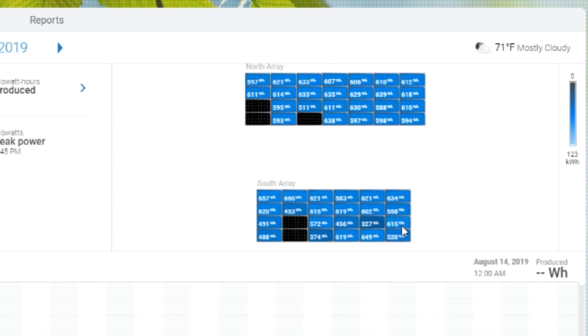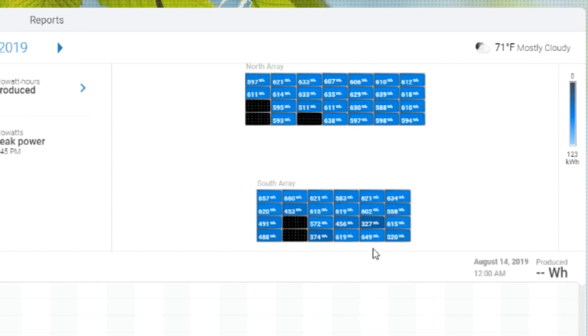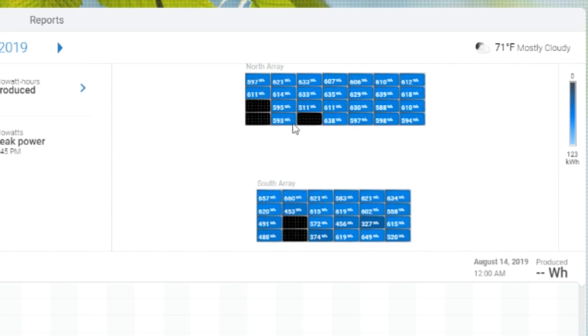Now, I know for a fact that there's no shading here, and it seems to be consistent, this low production. So it gives me a pretty good idea that this system has some issues, aside from just these obvious ones, these obvious inverters or panels that aren't producing anything.